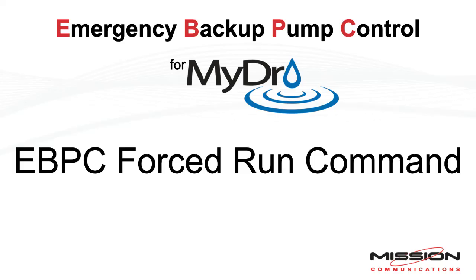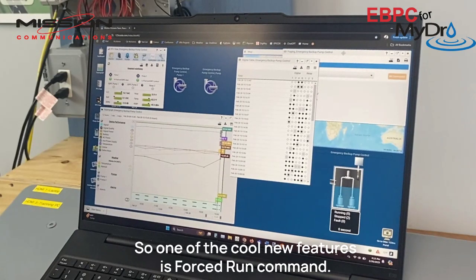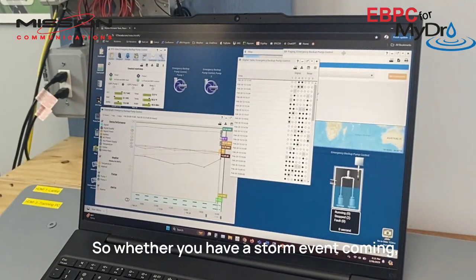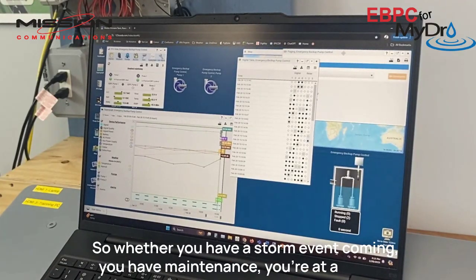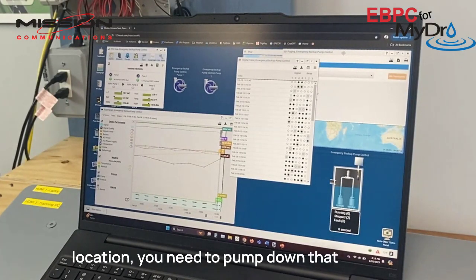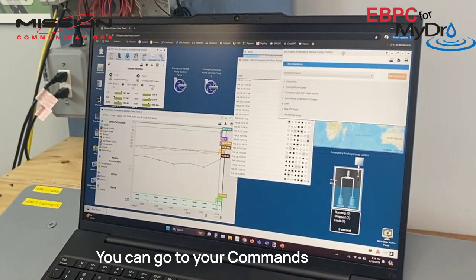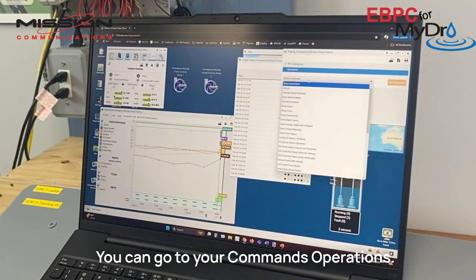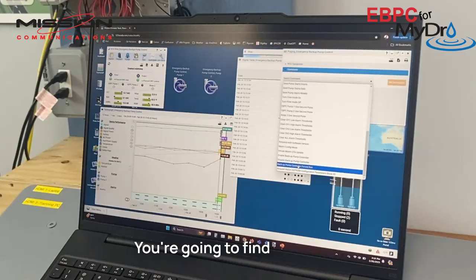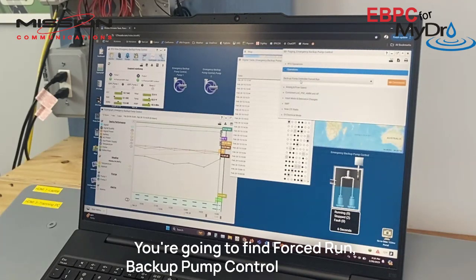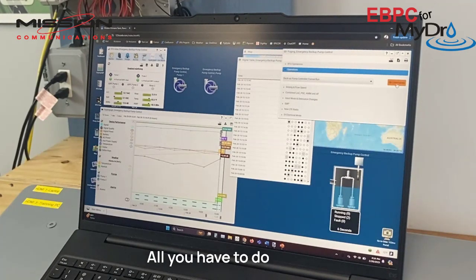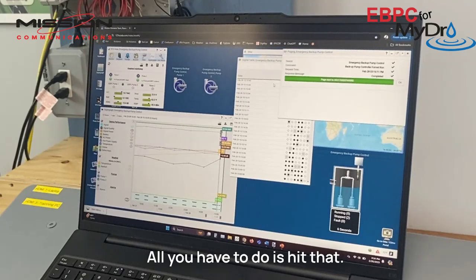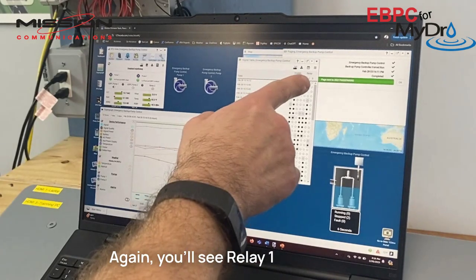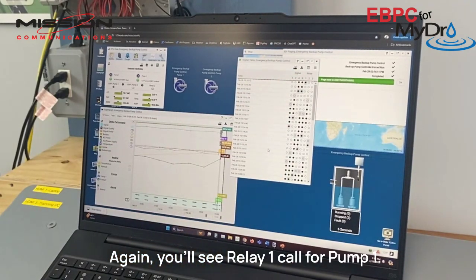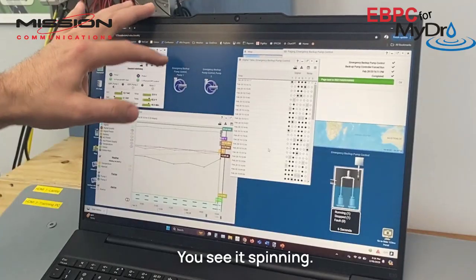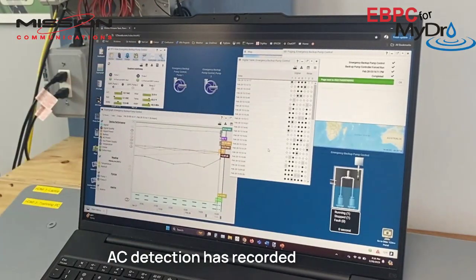So one of the cool new features is force run command. So whether you have a storm event coming, you have maintenance, you're at a remote location, you need to pump down that lift station, you can go to your commands, operations, you're going to find forced run, backup pump control forced run. All you have to do is hit that. Again, you'll see relay 1 call for pump 1. We see it spinning. AC detection has recorded the current.